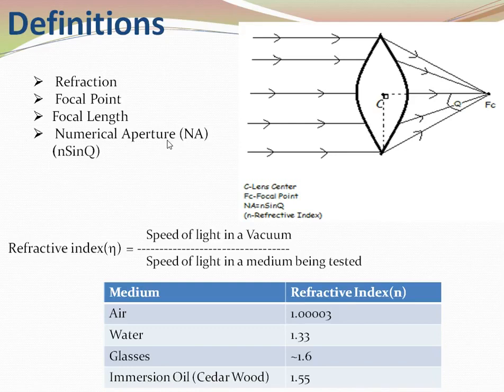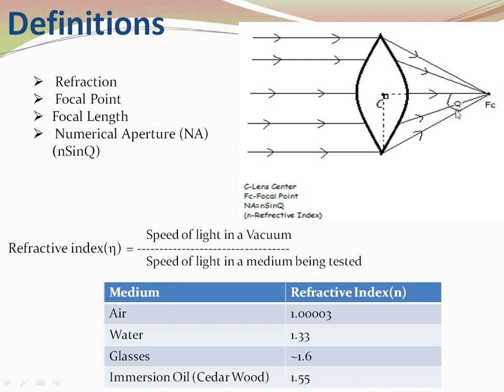Numerical aperture is a mathematically calculated formula. To understand it, we need to learn about the intake angle first. The intake angle is the angle between the two farthest rays focusing on the focal point. For numerical aperture (NA), we take the sine value of half the intake angle. So NA equals the refractive index multiplied by the sine of half the intake angle.